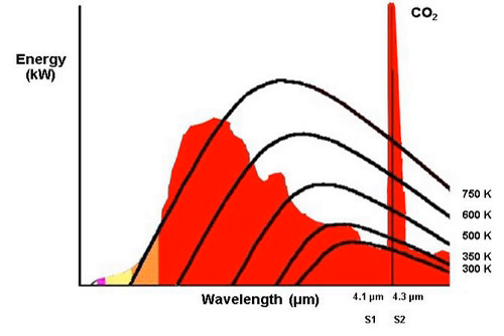IR3 flame detection. Multi-infrared detectors make use of algorithms to suppress the effects of background radiation, blackbody radiation. Again, sensitivity is reduced by this radiation. Triple IR flame detectors compare three specific wavelength bands within the IR spectral region and their ratio to each other.